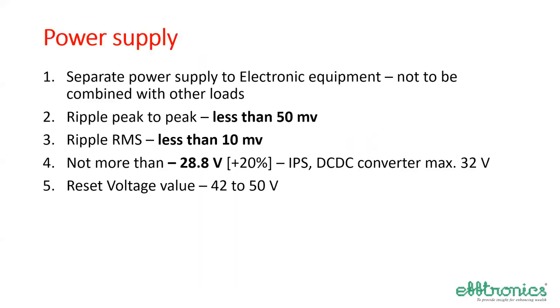Now let us look at power supply. Separate power supply is to be used for electronic equipment like SSDAC or electronic interlocking. Because if you connect any inductive load, whenever power supply is cut off to that inductor, it gives a pulse, as I have told about relays. That is why a separate power supply has to be connected to this equipment. Especially for axle counter equipment, if you look at the specification, it says ripple. The DC voltage may be 24 volts, but if it varies by 50 millivolts more or less, it is not permitted. Peak to peak is 50 millivolts, and if you convert it into RMS, it should be less than 10 millivolts. Those are the stringent conditions to be fulfilled by the power supply system.